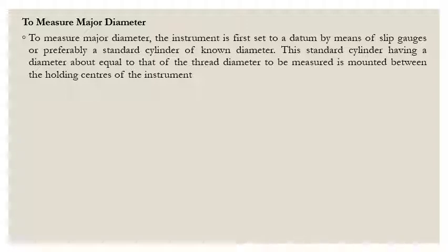This standard cylinder, having a diameter about equal to that of the thread diameter to be measured, is mounted between the holding centers of the instrument.